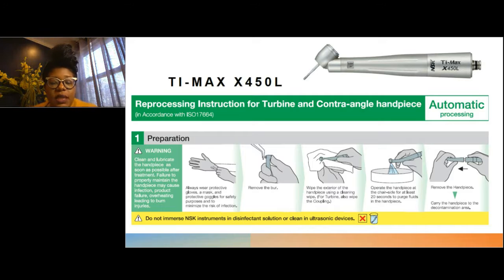So if you can see here, the manufacturer, in bold and in yellow, says don't immerse this in any kind of disinfectant solution or clean in an ultrasonic. So my key thing is not all devices can go into the ultrasonic. The IFU will tell you that. It will let you know the limitations of your device, what it can do, what it can't do, what you should do, and what you should not do.